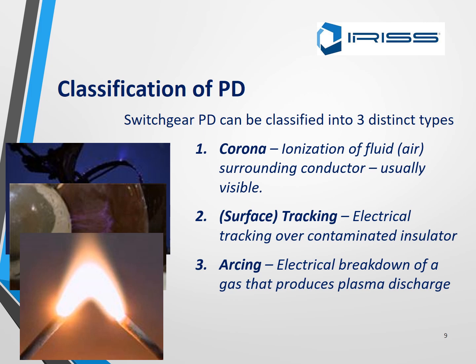Surface tracking is the electrical tracking over contaminated insulators. With surface tracking you can actually physically see it, you can hear it through ultrasound, and you will also be able to pick up small heat signatures via infrared. Arcing has a distinctive sound and can definitely be picked up by PD, by ultrasound, and by infrared.